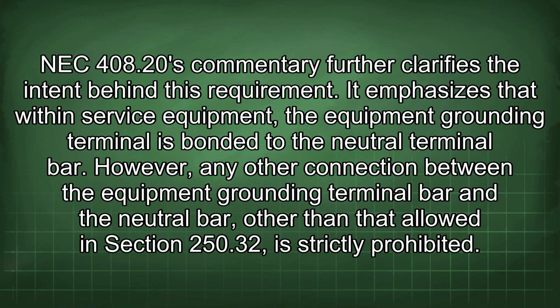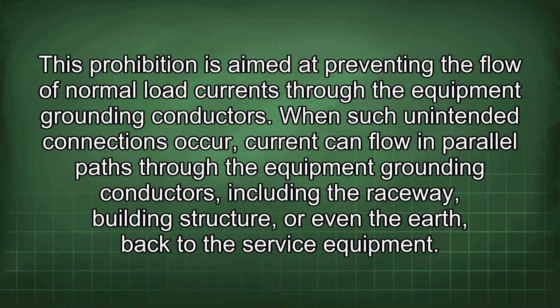NEC 408.20's commentary further clarifies the intent behind this requirement. It emphasizes that within service equipment, the equipment grounding terminal is bonded to the neutral terminal bar. However, any other connection between the equipment grounding terminal bar and the neutral bar, other than that allowed in Section 250.32, is strictly prohibited. This prohibition is aimed at preventing the flow of normal load currents through the equipment grounding conductors. When such unintended connections occur, current can flow in parallel paths through the equipment grounding conductors, including the raceway, building structure, or even the earth, back to the service equipment.